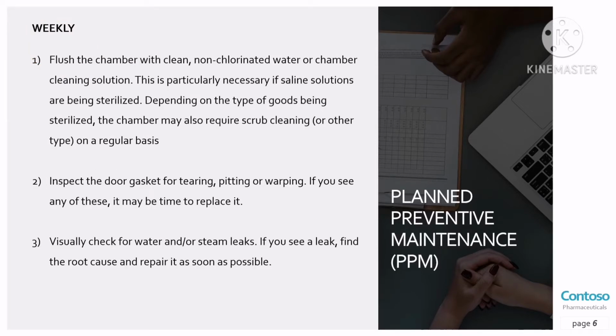Next, planned preventive maintenance for autoclave weekly. First, you must flush the chamber with clean, non-chlorinated water or chamber cleaning solution. This is particularly necessary if saline solutions are being sterilized. Depending on the type of goods being sterilized, the chamber may also require scrub cleaning or other types of cleaning on a regular basis. 2. Inspect the door gasket for tearing, pitting, or warping. If you see any of these, it may be time to replace it. 3. Visually check for water and/or steam leaks. If you see a leak, find the root cause and repair it as soon as possible.